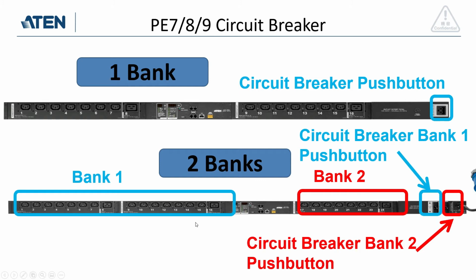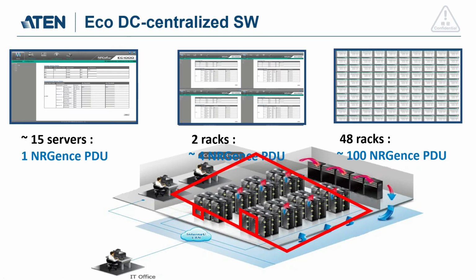If you have a larger product, you can have two banks, each with its own circuit breaker. So if something happens with a server in bank 2, like a short circuit, only that bank goes down. You fix the short circuit, then press the button to reopen the circuit to the other servers.